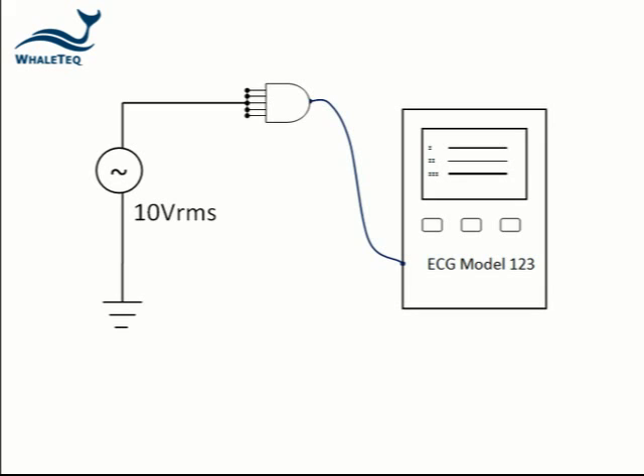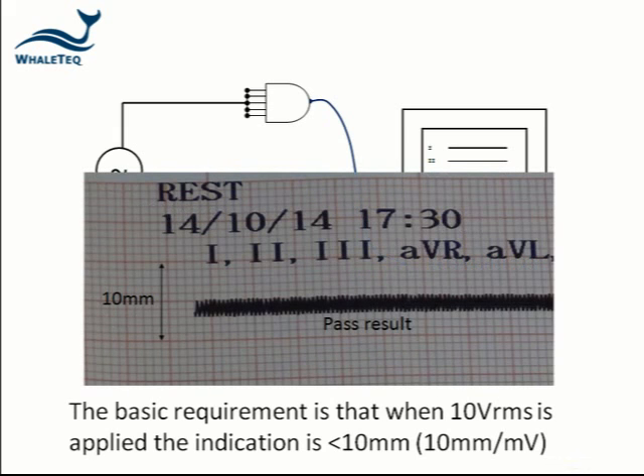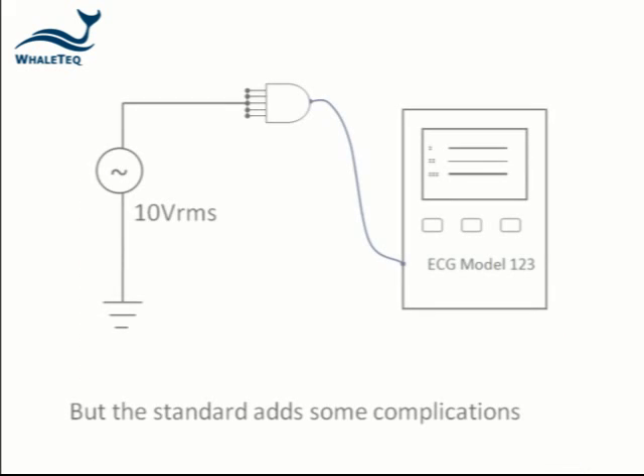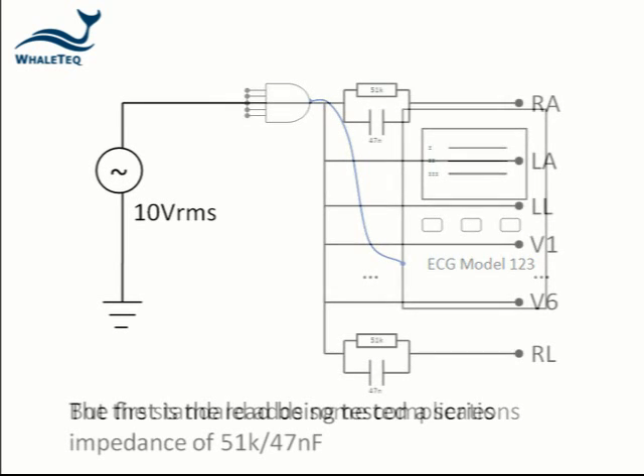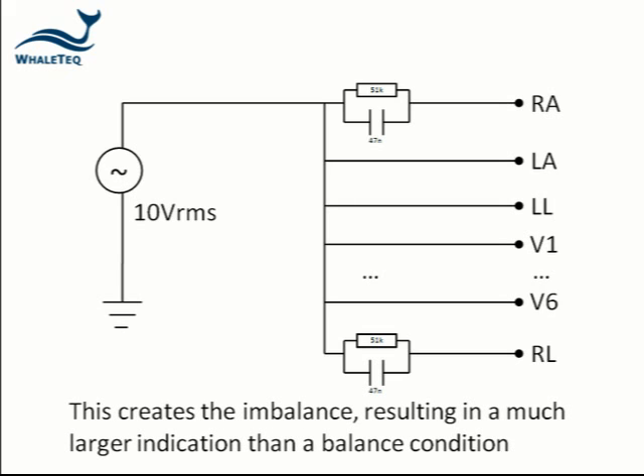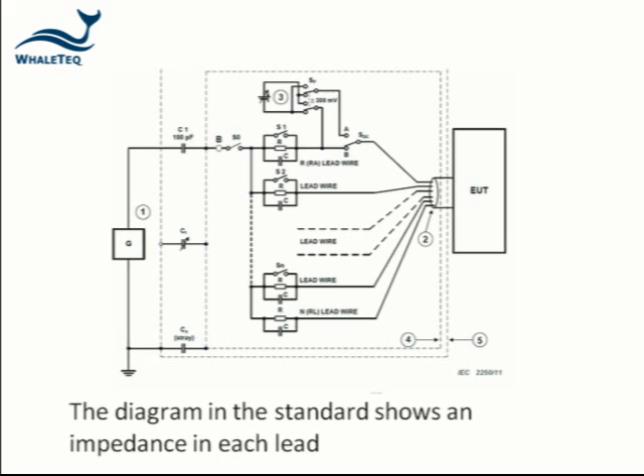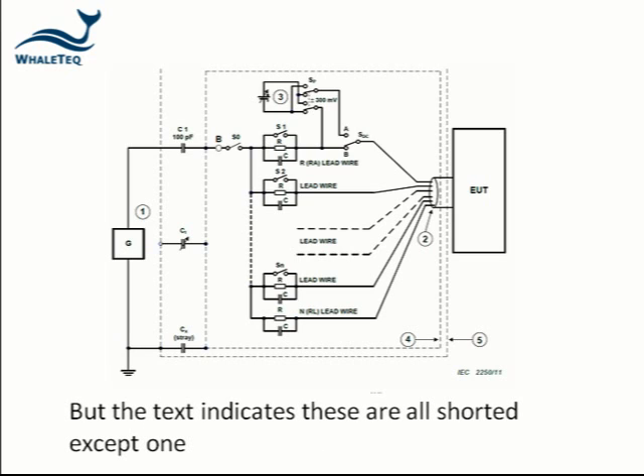The basic requirement is that when 10 volts RMS is applied, the equipment should indicate less than 10 mm with a normal sensitivity of 10 mm per mV. But the standard adds some complications. The first is that the lead electrode being tested must have a series impedance of 51k and 47 nF. This creates the imbalance and causes a much larger indication than the balanced condition. This impedance also appears in the right leg, although the effect of this is usually negligible. The diagram in the standard shows an impedance with a switch in each electrode, but the text indicates that all switches are shorted except for one.